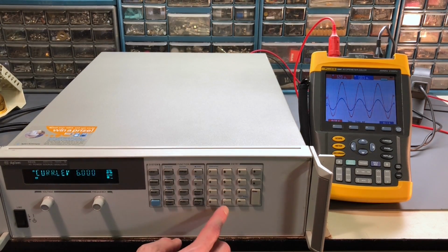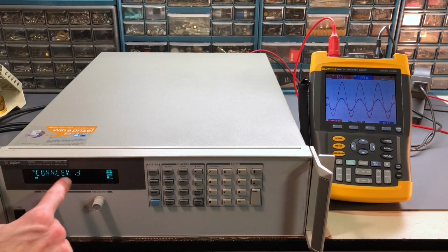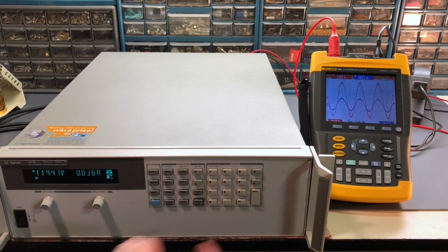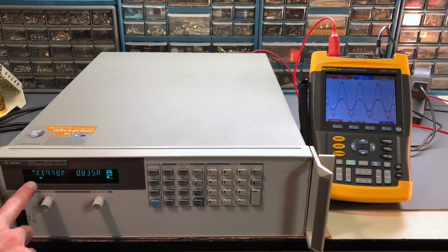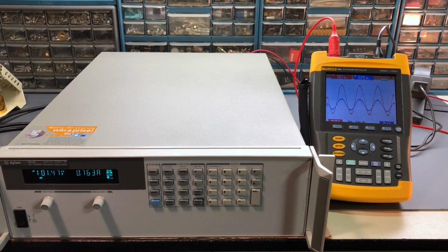So I'll make this something smaller, we'll go 0.3, so 1/3 of an amp roughly. Hit enter. So now it's going to detect that that current value is above 0.3 amps. We can see it's already gone into the constant current mode, so that looks good. And it should begin to program down to match that 0.3 amp value. Yep, there it goes. You can see it's dropping.